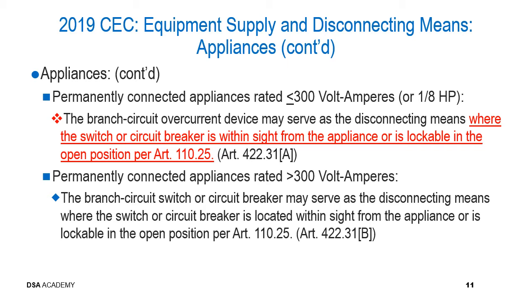In these situations, the branch circuit switch or the circuit breaker may serve as the disconnecting means where the switch or circuit breaker is located within sight from the appliance or is lockable in the open position per Article 110.25. This comes from Article 422.31(B), and as you can see, this is very similar to the newly revised or newly amended requirements for permanently connected appliances that are rated less than or equal to 300 volt amperes or 1/8 horsepower.